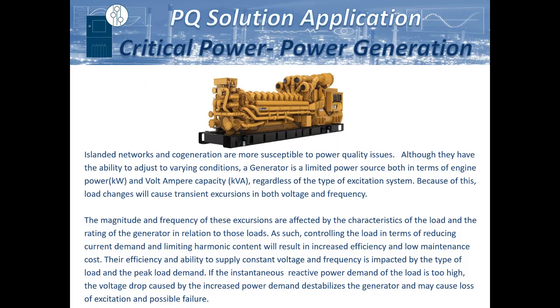This also holds true for applications that utilize cogen, or if they are generator powered. There are generator manufacturers that pretty explicitly state that you cannot run a power factor correction system on a generator network, because they don't want the system to be overcapacitive, because that actually induces additional heat and wear and tear on the generator. That is with the exclusion of us.